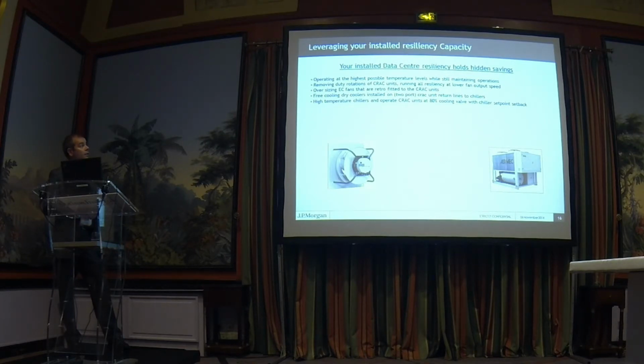Free cooling dry coolers on the return ports and return lines from your CRAC units. If you run a 2-port control on a CRAC unit, 2-port is like water in, tap, water out. On the water outside, if you run at 22 degrees, you'll get 22, 23 degree water out. You pass that water straight through a dry cooler before it enters your chiller system. So anything below 22 degrees, you're going to get free cooling out of it.